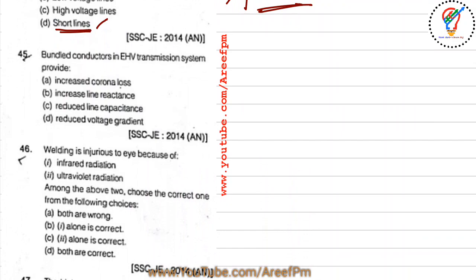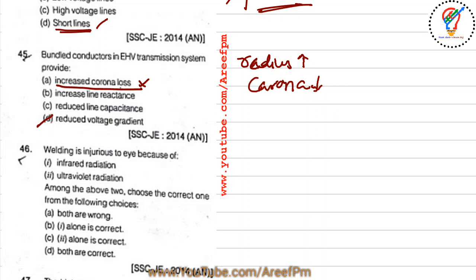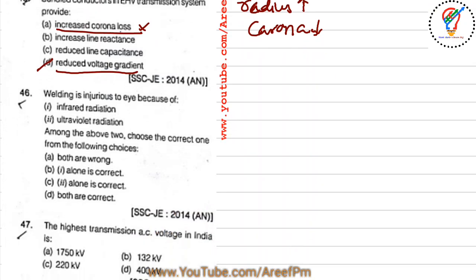Question 45: bundle conductors in EHV transmission systems — the main effect is an increase in the effective radius of the phase conductors. This increased radius decreases the surface voltage gradient, thereby reducing corona.